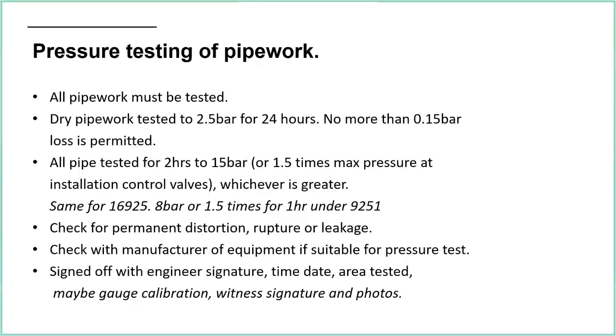So it would be a good idea, I think, for the sprinkler contractor to do that test well in advance of final commissioning, so that there's a chance for things to be rectified if any problems are found. That is exactly the same for 16925. So BSEN 16925, the residential standard, says exactly the same: 2 hours, 15 bar or 1.5 times max pressure. Under 9251, it's 8 bar or 1.5 times maximum pressure. So again, it adds up to the same thing, really. And that's only for 1 hour rather than 2 hours. So yeah, it's a bit of a difference.